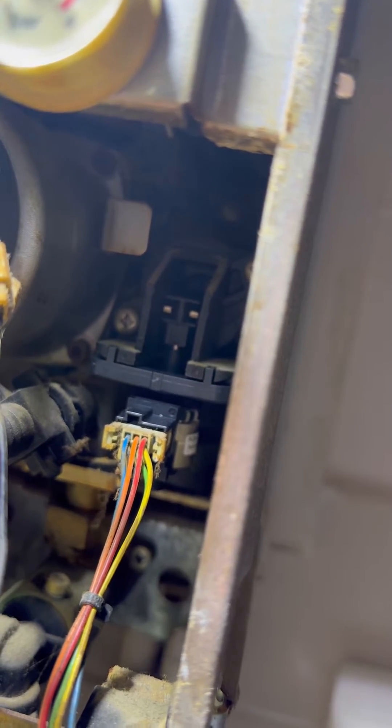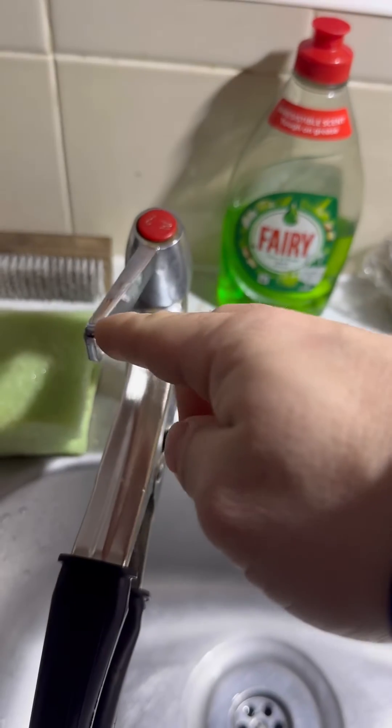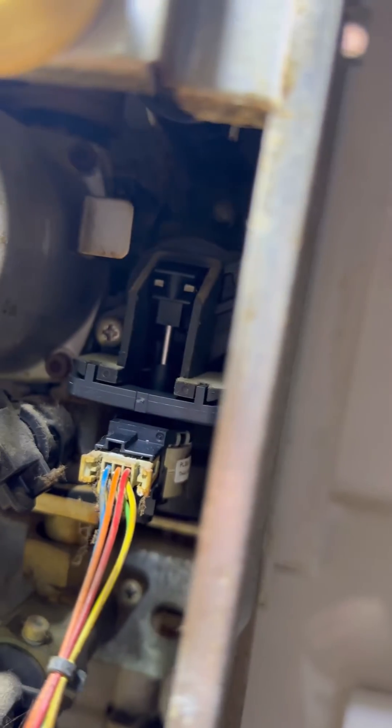You can see movement in it straight away, which is a good sign. Now I'm going to open the hot tap, and that motor should go all the way to the top — there we go. That means it's opened it up to flow around the hot water around the plate.